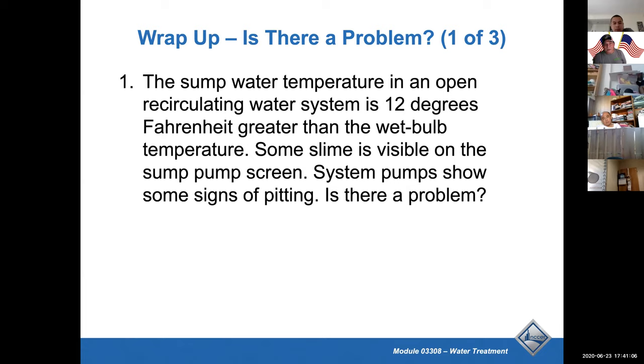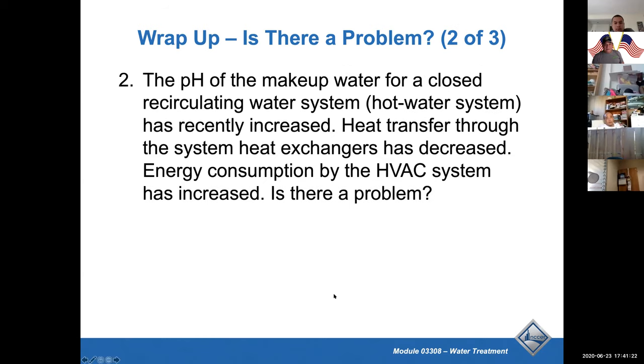Okay, and this first one. Water temperature in an open recirculating water system is 12 degrees greater than the wet bulb. Some slime is visible at the pump screen. Is there a problem? Yes. That is a problem.